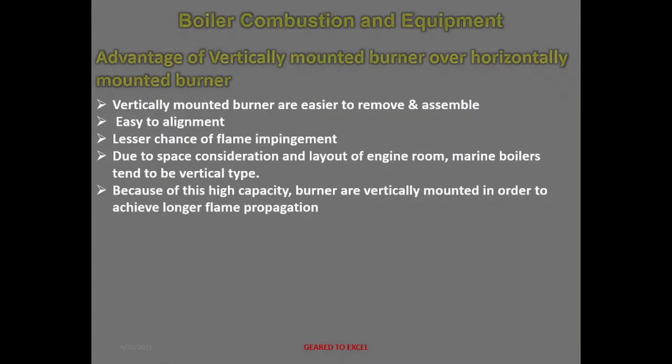Advantages of vertically mounted burners over horizontally mounted burners: vertically mounted burners are easier to remove and assemble, easier to align, and have lesser chances of flame impingement. Due to space considerations and the layout of the engine room, marine boilers tend to be vertically stacked. High-capacity burners are vertically mounted in order to achieve longer flame propagation.